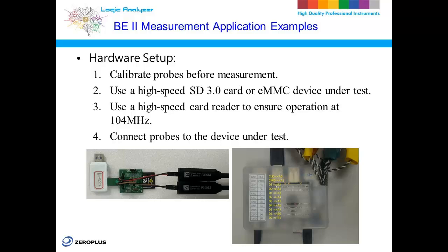Once the hardware setup is complete, perform a simple test to verify that everything is functioning correctly. A quick signal measurement can confirm that the probes, card reader, and DUT are all properly connected and working. Once you observe a stable signal waveform, you're ready to proceed with detailed measurements and analysis.